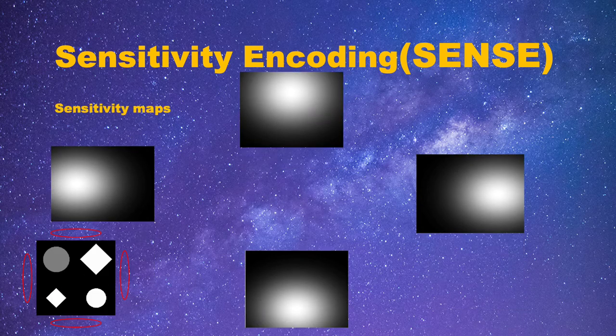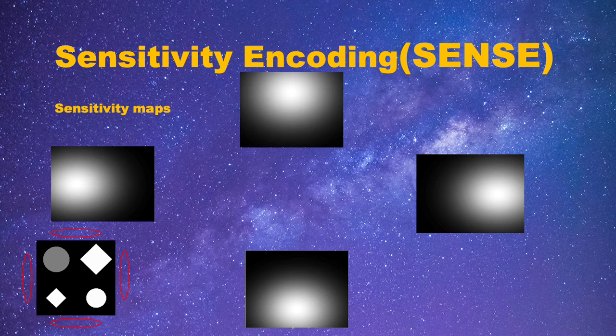For example, the coil on the left will be better at acquiring signals from the left part of the object. We can use these images to get a separate image called the sensitivity map. The sensitivity maps describe where this coil can acquire more signal at the whole field of view.